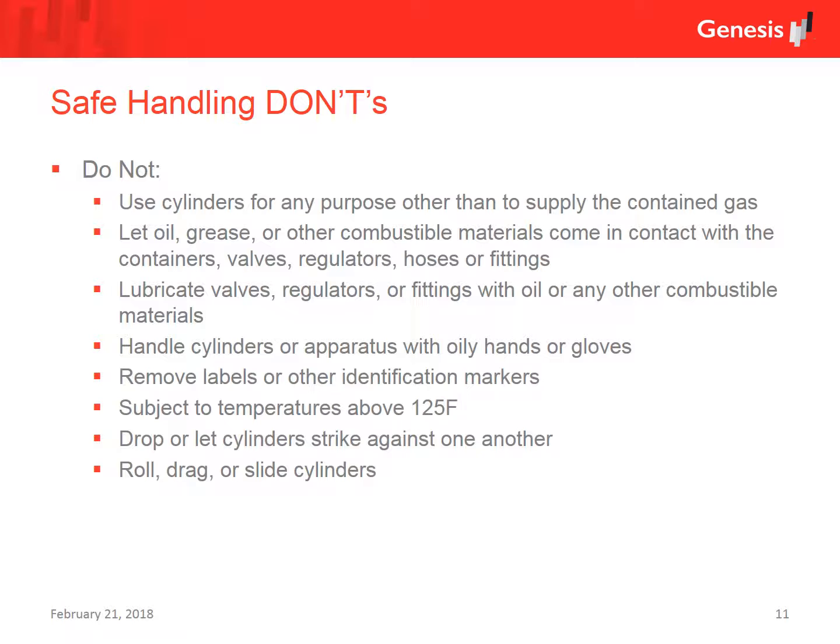Safe handling don'ts. Don't use cylinders for any other purpose than what they're intended for. Don't let any flammable or combustible materials come in contact with the containers, valves, or regulators. Never lubricate the valves, regulators, or fittings. Do not handle cylinders or apparatus with oily hands or gloves. Never remove labels or other identification markers. Never utilize gas cylinders in temperatures that exceed 125 degrees Fahrenheit.